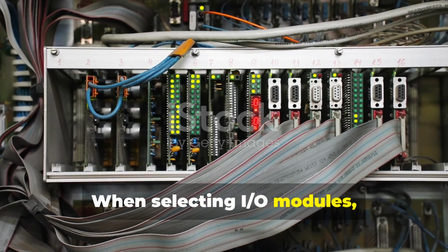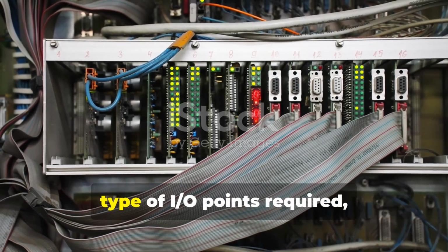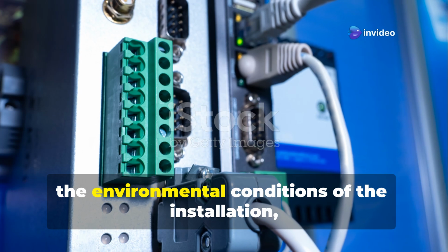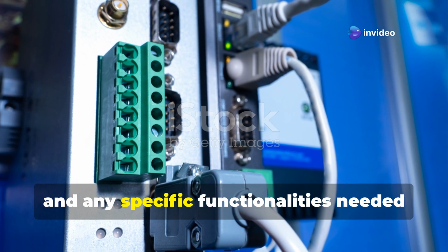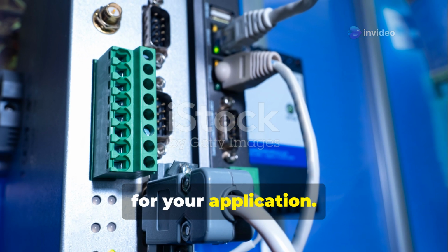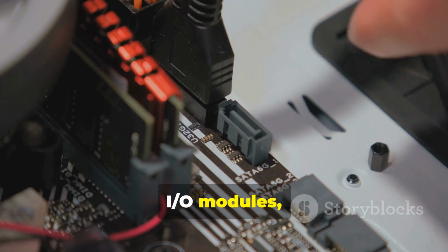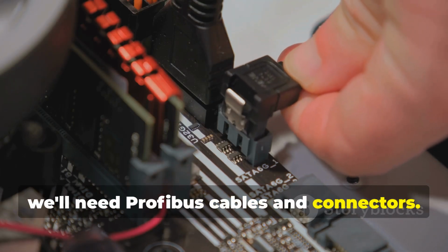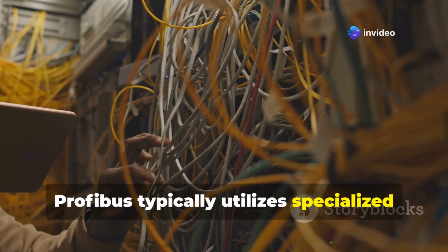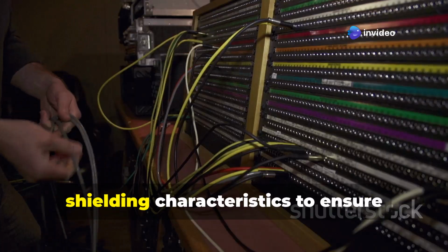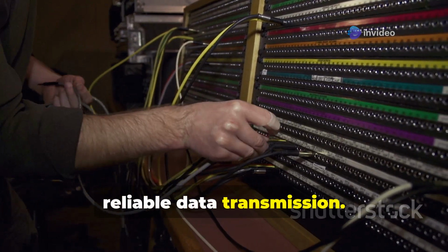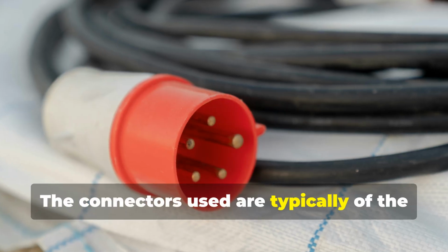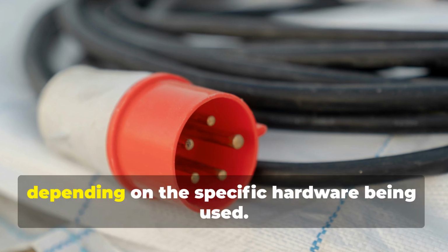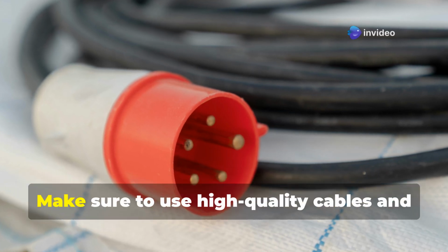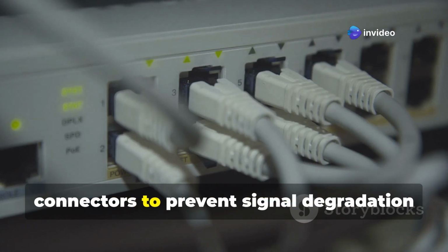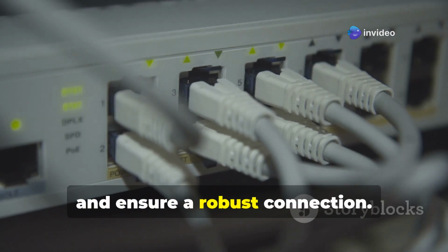When selecting I/O modules, consider factors such as the number and type of I/O points required, the environmental conditions of the installation, and any specific functionalities needed for your application. To physically connect the PLC and remote I/O modules, we'll need Profibus cables and connectors. Profibus typically utilizes specialized cables with specific impedance and shielding characteristics to ensure reliable data transmission. The connectors used are typically of the DB9 or M12 type, depending on the specific hardware being used. Make sure to use high-quality cables and connectors to prevent signal degradation and ensure a robust connection.